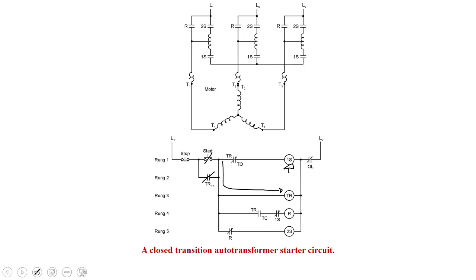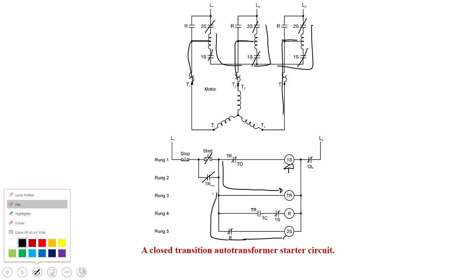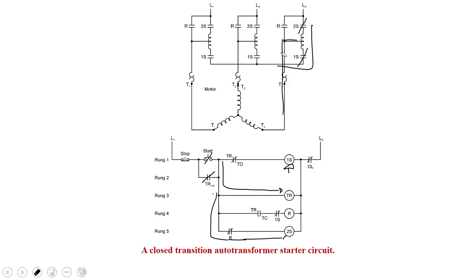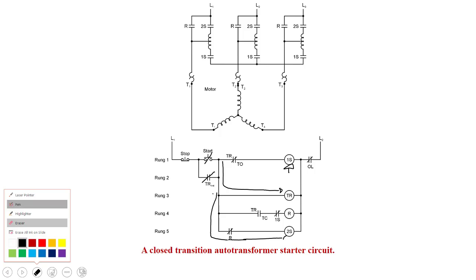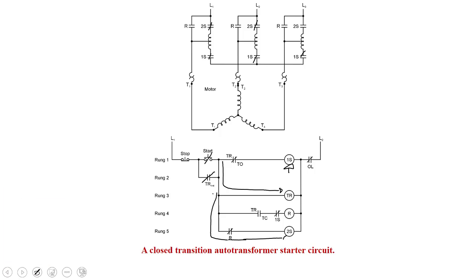And so let's go ahead and draw 1S closed. As you see here, it hooks up the 3 auto transformers basically in Y. What else would happen here is current would also flow down. And we see we have a normally closed R contact, so 2S would also energize at the same time. So here are our 3 auto transformers connected up in Y, and there's the tap off the middle of them to go to the motor on each one right there. All right. So right now the motor is started and it's operating at a reduced voltage when 1S and 2S are closed. It's just like that.